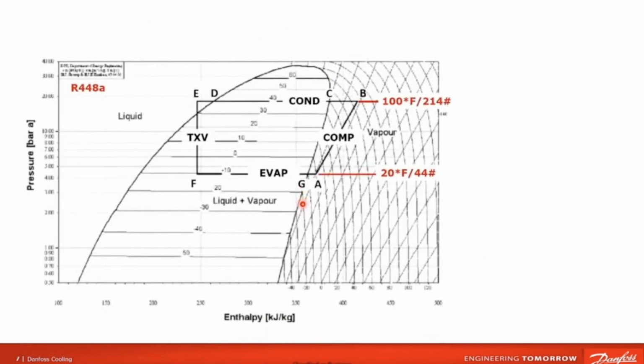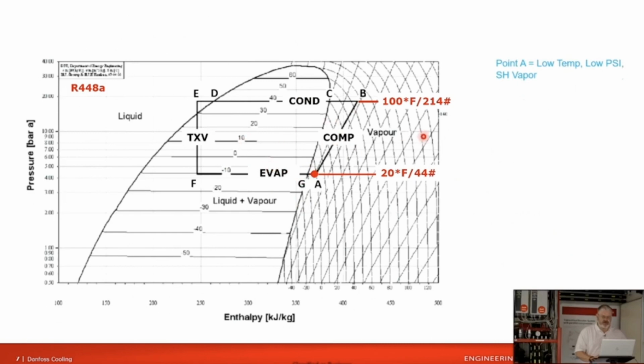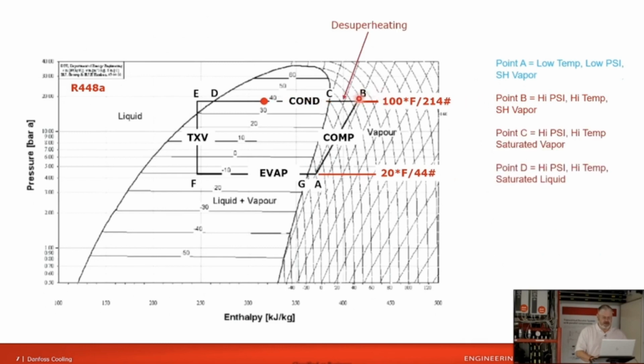So we're going to take that same cycle and now look at it on a pH diagram to try and connect those dots. Same cycle. We're just showing it now so you can reference vapor and liquid and the dome liquid and vapor combination. So we went from the suction inlet of the compressor, across the compressor, absorbed the heat of compression. Now we're back up to the condenser as a high pressure, high temperature, superheated vapor. We desuperheat some, then we condense.